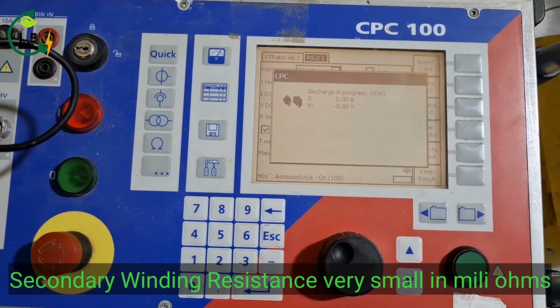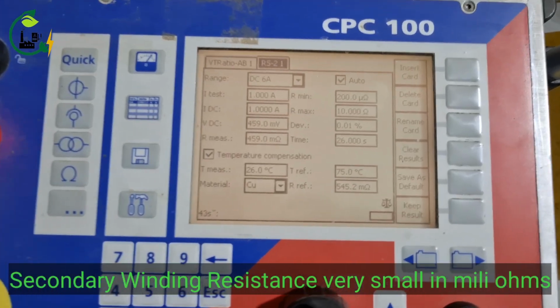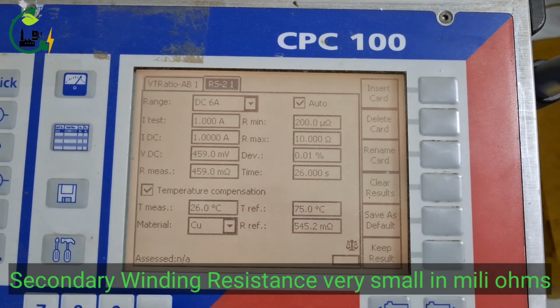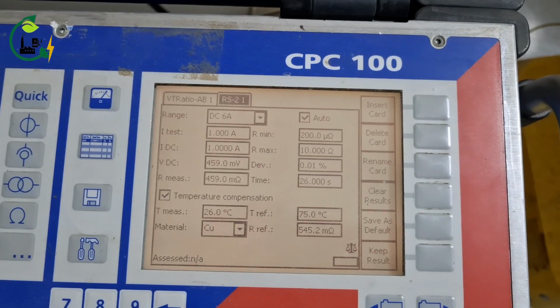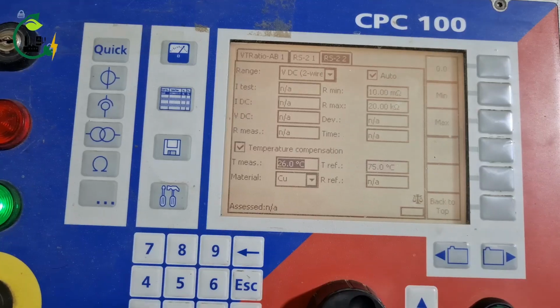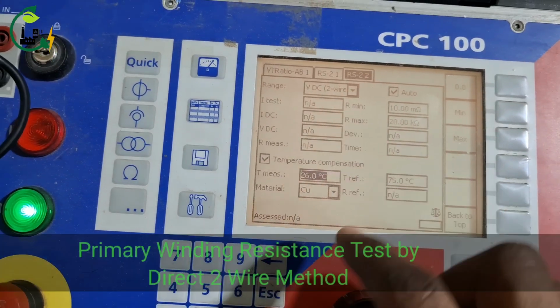After de-energization it will show you the secondary winding resistance. Why did we use the injection method? Because the winding resistance is very small to calculate accurately. So for the primary we can use a multimeter directly, or we can use the direct method. So here are the results: resistance 459 milliohm, and at 75 degrees.